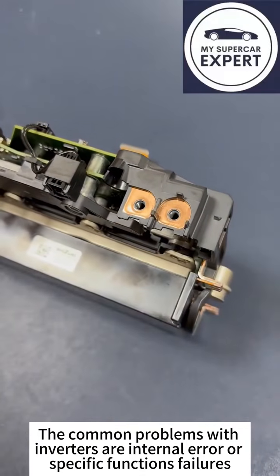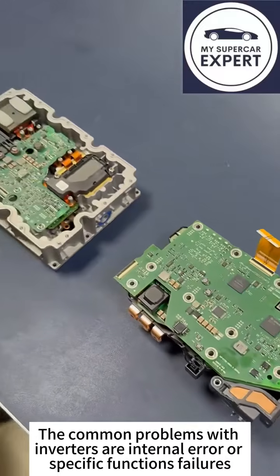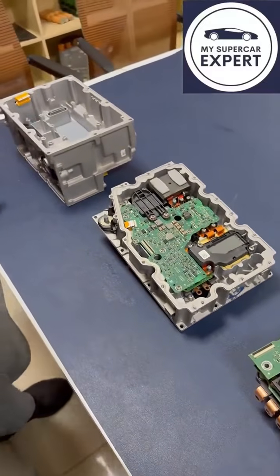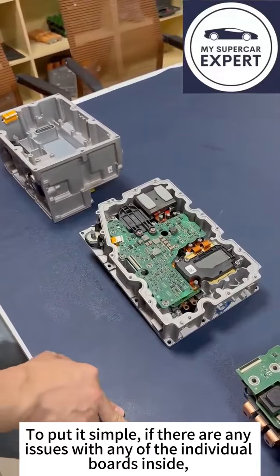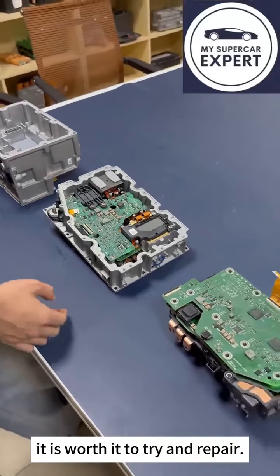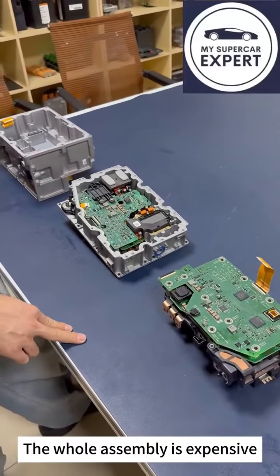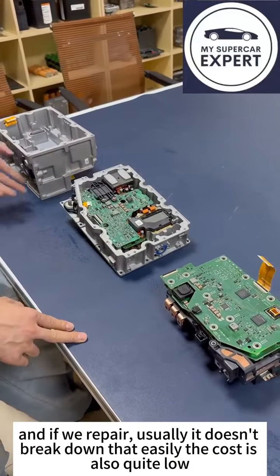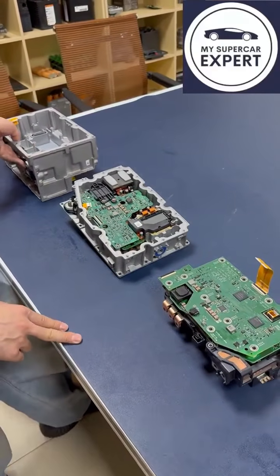The common problems with inverters are internal errors or specific function failures. To put it simply, if there are any issues with any of the individual boards inside, it is worth trying to repair, since the whole assembly is expensive. And once repaired, it usually doesn't break down that easily. The cost is also quite low.